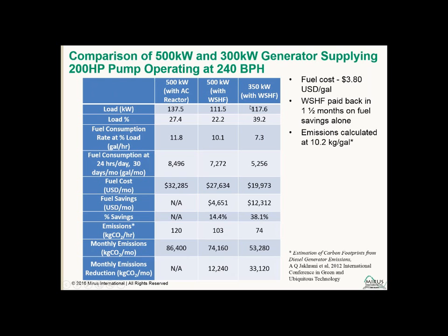Then when we look at the smaller generator, and again the customer decided to go with a 350 kilowatt, even though they could have gone smaller. The power consumption was 117 kilowatts. That was 40% loading, so slightly higher, closer to the optimal efficiency of the generator, which improved the fuel consumption further. So now we're only at 5,000 gallons per month, or $20,000 per month, a savings of $12,000. 38% reduction in fuel consumption.